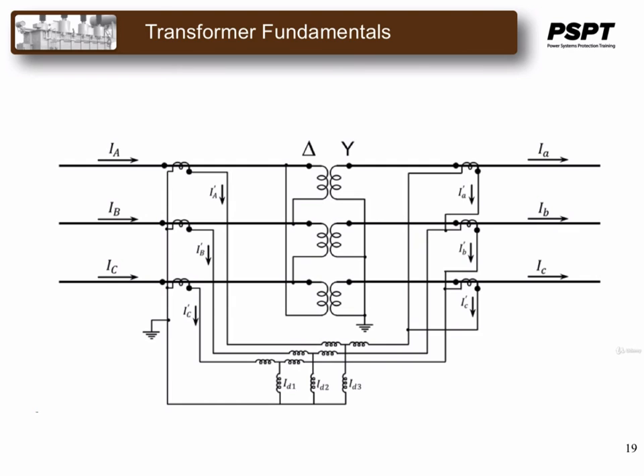This is another example where a differential relay protection is on a delta to Y transformer. The spot markings of the instrument transformers, the CTs in this case, are very clearly visible, and including the spot markings of the power transformer for which it is protecting.